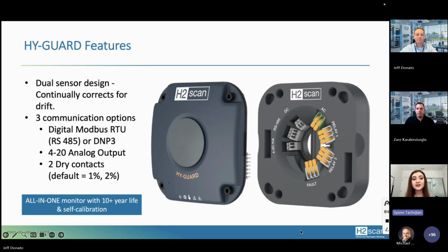The device supports three communication options, including digital communications through Modbus RTU over RS-485 or DNP3, a 4 to 20 milliamp analog output, and two dry contact relays with default alarm points at 1% and 2% hydrogen.